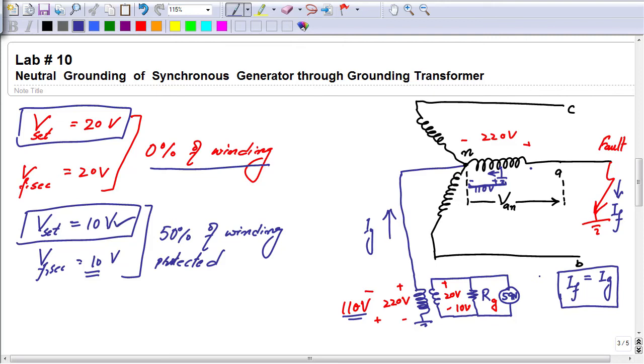So if we keep on reducing the value of Vset, the protected portion of the winding will keep on increasing. Let's say I make Vset equal to 5 volt. Without any discussion, we can say that this setting would protect up to 75% of the winding. What does it mean? If a fault occurs from 0, this neutral point, up to 25% of the turns, that fault would not produce sufficient voltage to trip the relay. But if the fault is from 25% up to 100% of the turns, this is the protected region and this is the unprotected region. So 75% of the winding is protected.